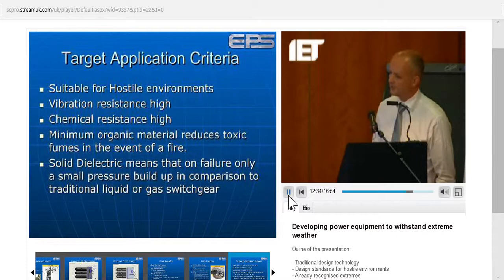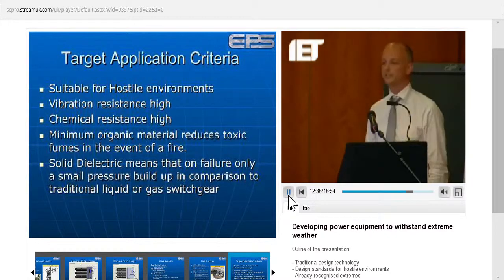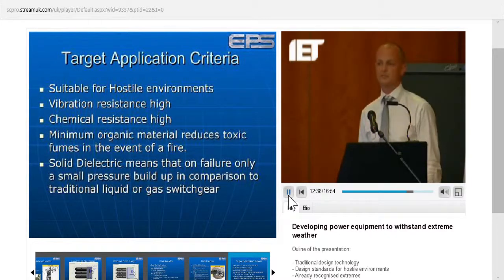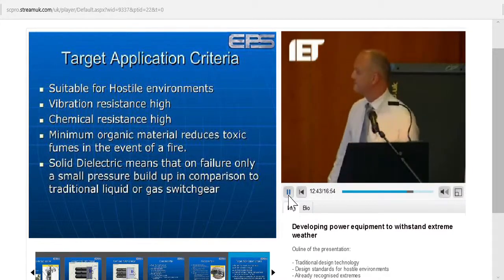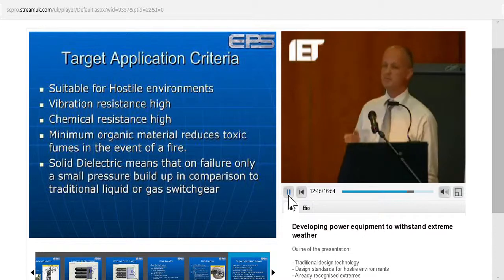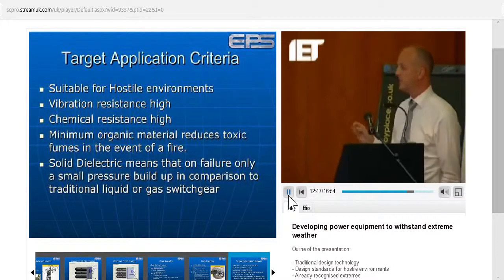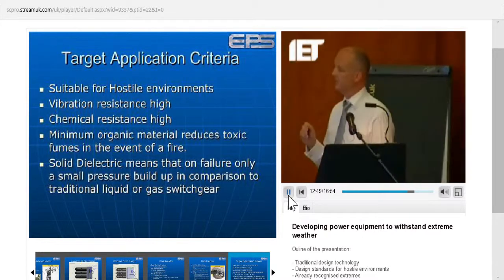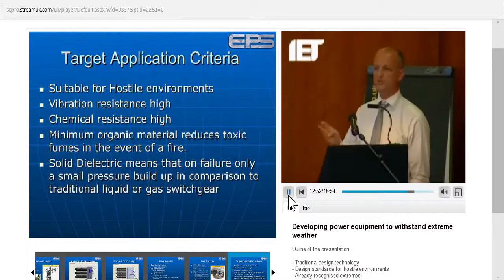If you were to submerge it completely in petroleum or oil, you would probably only get a year or so's life out of it, but you wouldn't have that situation for most sites. The fact that it has a minimum amount of organic material in it means that if there is a dielectric failure, there's less likely to be a large explosion.